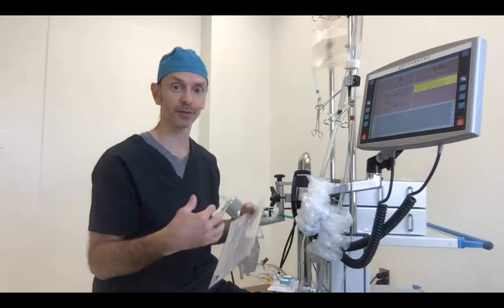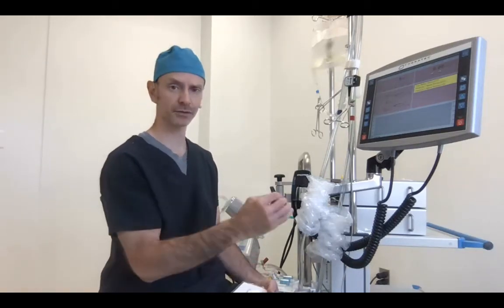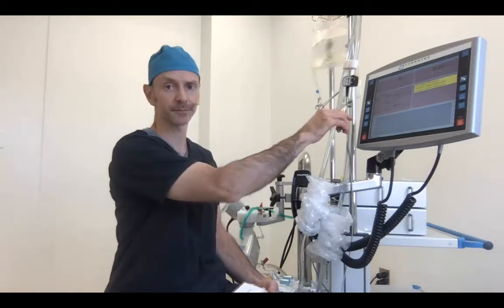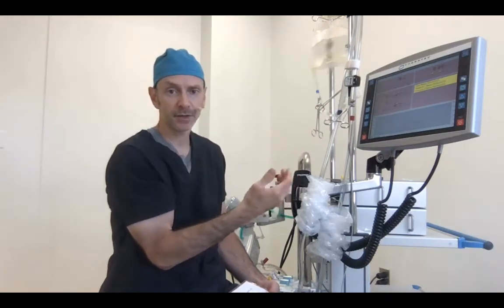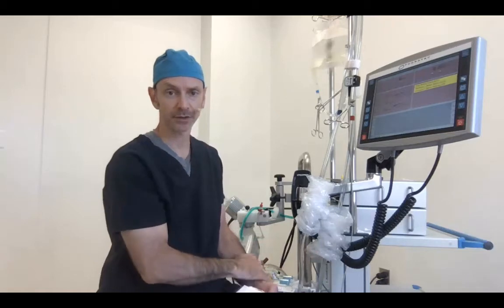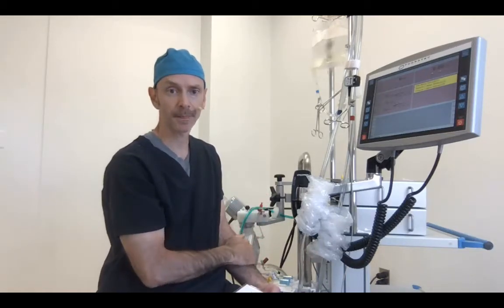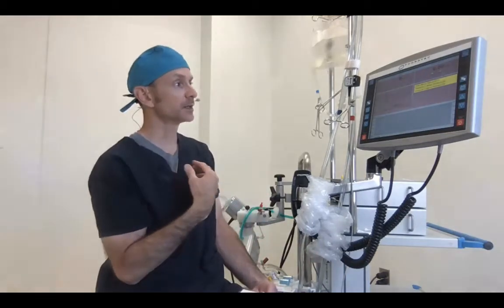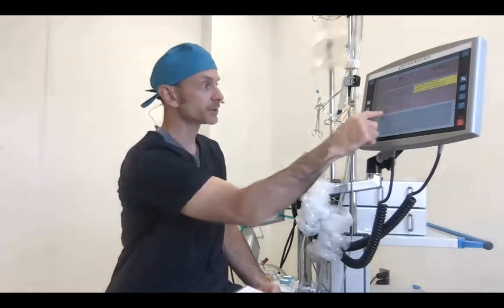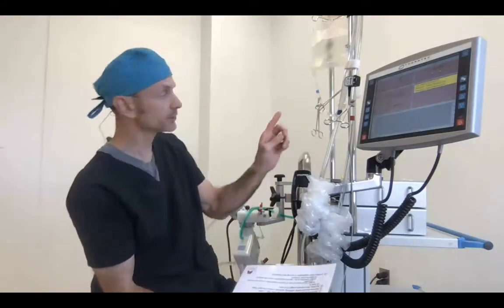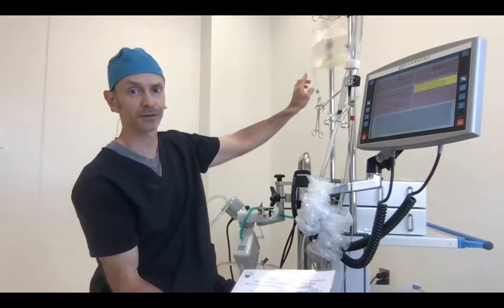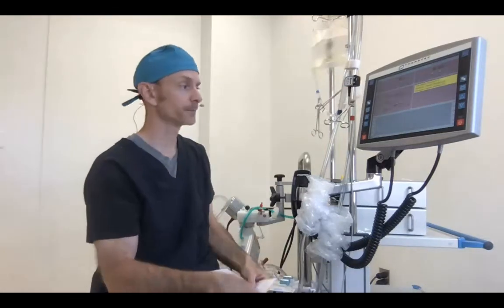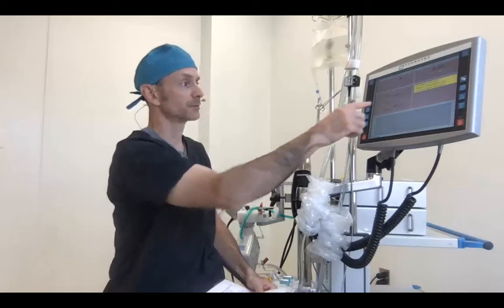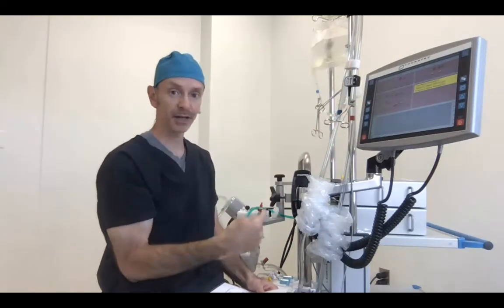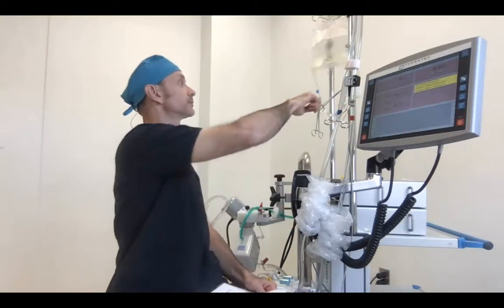This condition is a replacement for what the instructions for the pump say, which is you have to have a certain RPMs before you take this clamp off. And the manufacturers give you a number like 1,000 or 2,000, and it's a generally safe number. But we could be more sensitive to that. And here the situation would be you've got these line pressures, and today we're just hooked up to a bag over here, so we're just getting a static number. But if this pressure was being generated by the patient, then let's see, where are we?